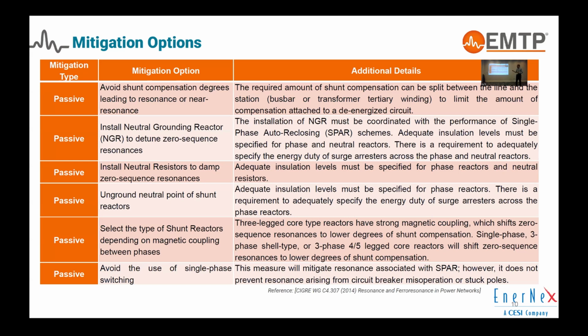Another passive option would be to include a neutral grounding reactor, which is going to detune that resonance point. Also, a neutral resistor can be added in order to provide damping. There are other options as well, for example, ungrounded neutral or special shunt reactors. Each of these solutions would require a careful design because they might lead to another issue. And finally, it is recommended not to do single phase switching if you want to really avoid that issue. But still, in this case, unintended unbalanced operation can happen.